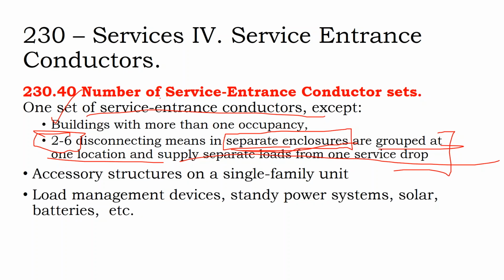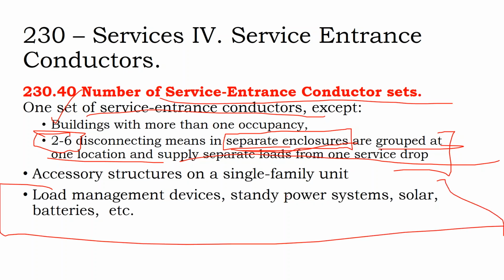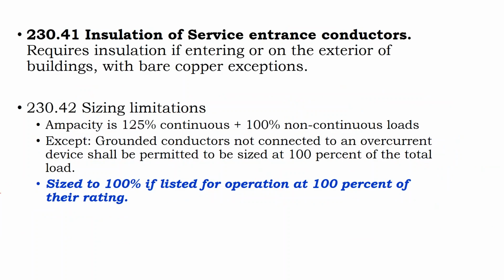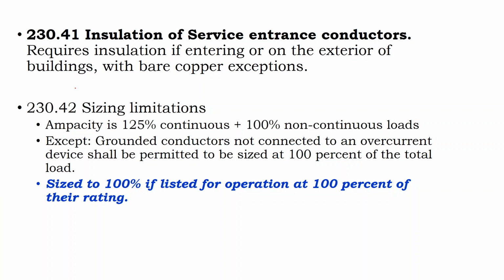You can have additional service entrance conductor sets for your standby systems and solar systems, and that might be if you want to have a battery up at your transformer that provides power during a blackout to everyone along the distribution circuit. You can run a new service entrance conductor set for that. So one thing to think about on that 6 disconnect switch rule, it's really not a hard and fast rule that you can only have 6 switches at this location. It's more that you can only have up to 6 switches for this specific type of use. So for your main service, you can have up to 6 disconnects with 6 service entrance conductors. For your backup power supplies, you can have up to 6 disconnects with your 6 service entrance conductors.